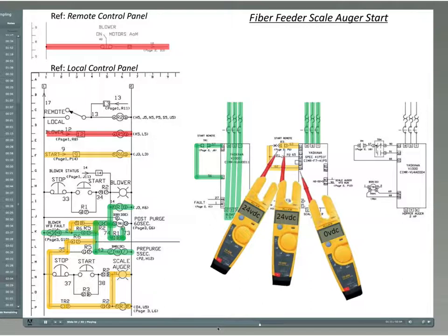With R3 active, DC voltage checks are made. The first check is made at R3 terminal 7. The expected good voltage is 0 volts DC. The actual voltage is 24 volts DC. The second check is made at R3 terminal 4. The expected good voltage is 0 volts DC. The actual voltage is 24 volts DC.